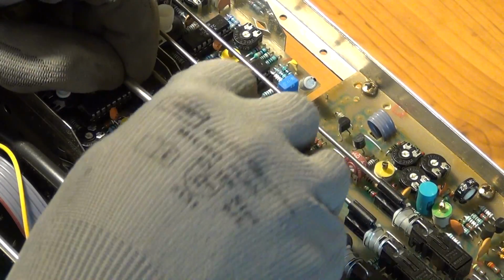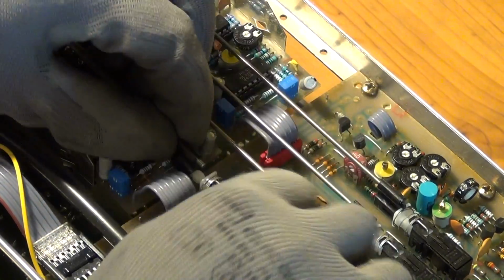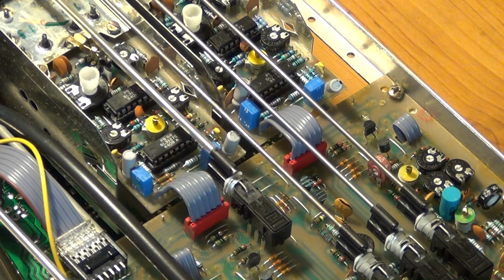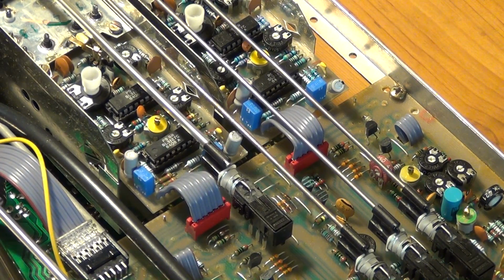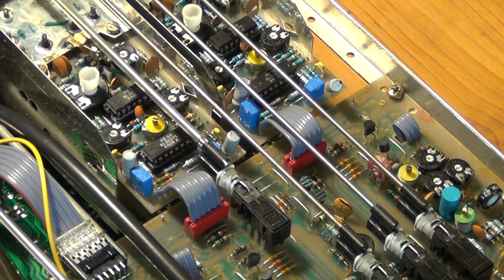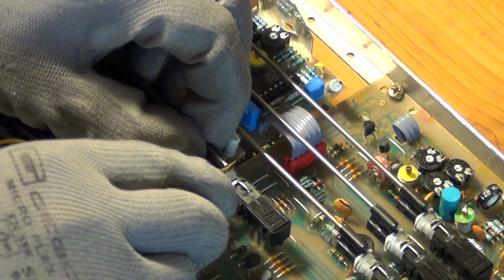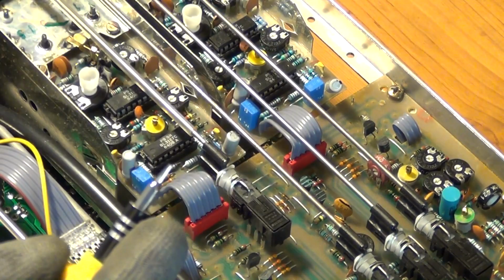You will find a lot of these rods inside these oscilloscopes, and that is because you want to keep all the switches and potentiometers and so on exactly in that space where they belong in the circuit, and you do not want to draw out the signal path to the front panel. That is in order to minimize the inductance of the paths and to minimize the noise that is coupled into the path and so on. But the oscilloscope was now in working order again, and I could go on to fix the next device.